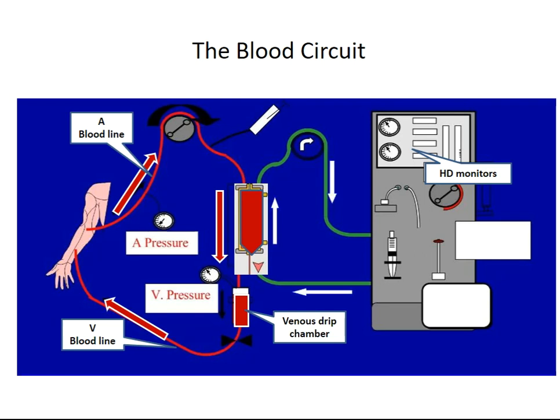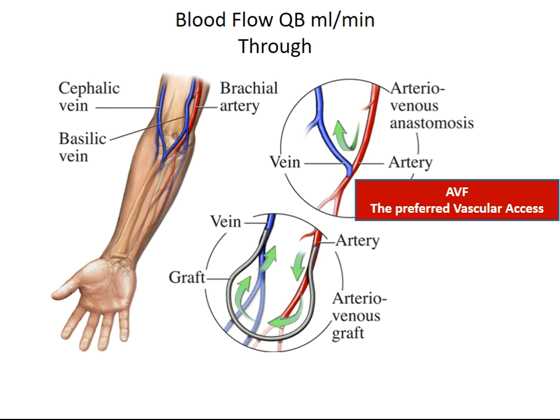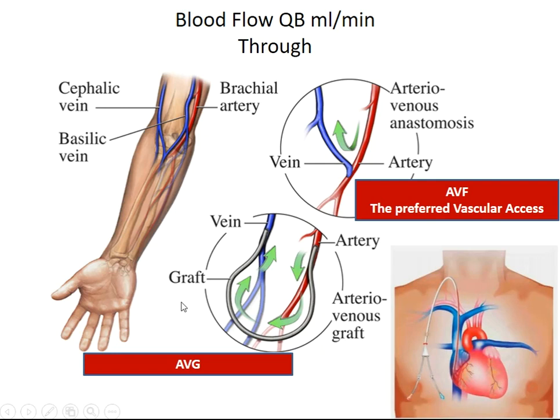Continuous monitors in the hemodialysis machine track the various extracorporeal circuit parameters. Blood flow goes through one of three vascular accesses: first and best is the arteriovenous fistula, which is the preferred vascular access; second is the arteriovenous graft; and lastly the central venous catheter, which is the last choice.